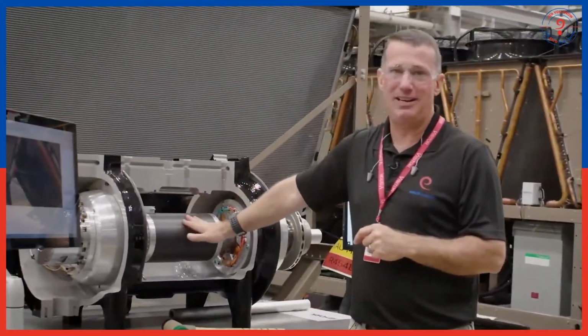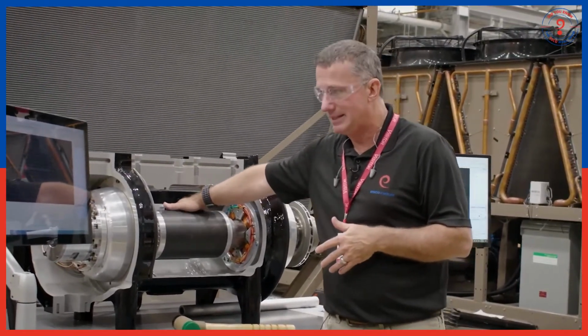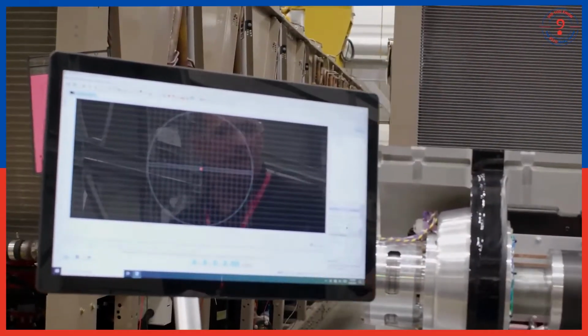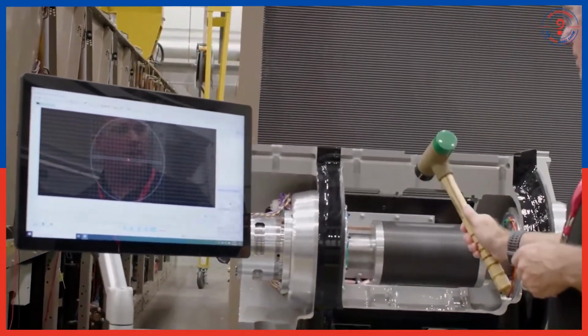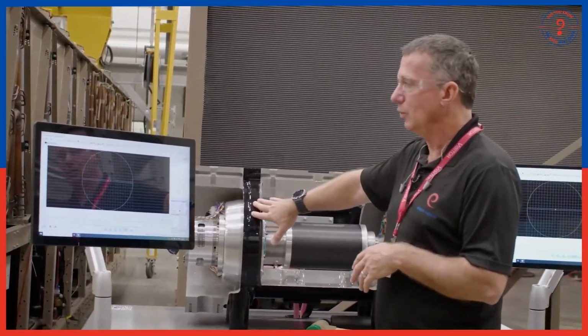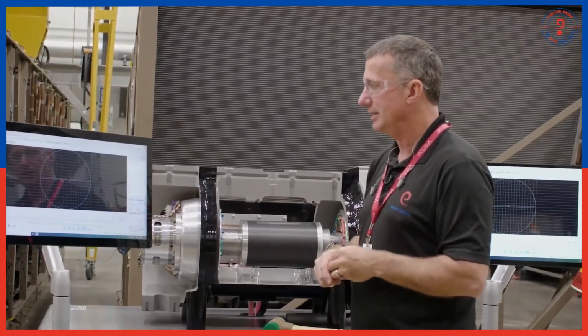So when we look at magnetic bearing technology, what we're doing is we're talking about removing those mechanical bearings. So we're removing friction as much as possible, and so we're using a magnetic center to maintain the rotation of our rotor. And so if you look on that chart, you're actually going to see the rotation of our rotor inside of our stator. And when we have shifts or changes in that rotor, it's actually going to show where the placement of that is. So if we had an imbalance of a rotor inside of that compressor due to a mechanical operation, the technology actually can shift that rotor. It can use the magnetic poles to recenter in very, very minimal increments to make sure that it keeps that rotor centered inside of that magnetic assembly.